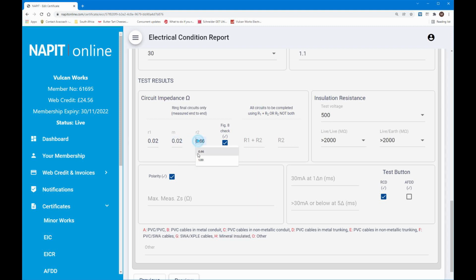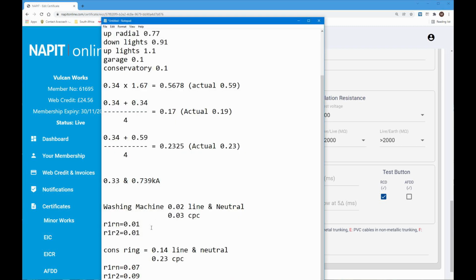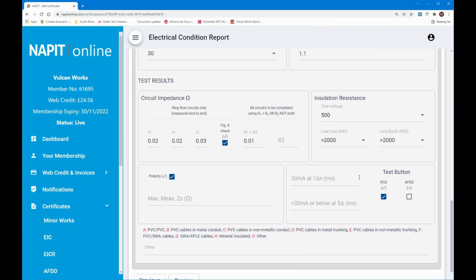And the reading for the R1, R2 was 0.03. And the actual reading here was 0.01. So very, very tiny readings within the realms of the 0.05 error. So I've got to put them down, but that's what they actually are. The tester would not go down any lower than that.